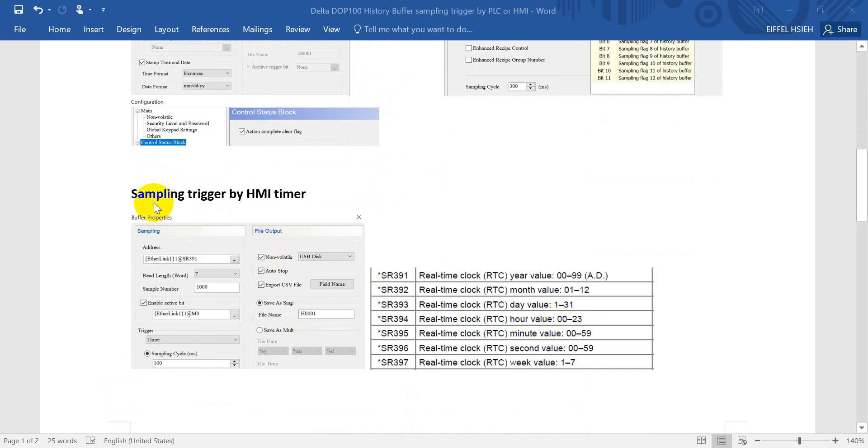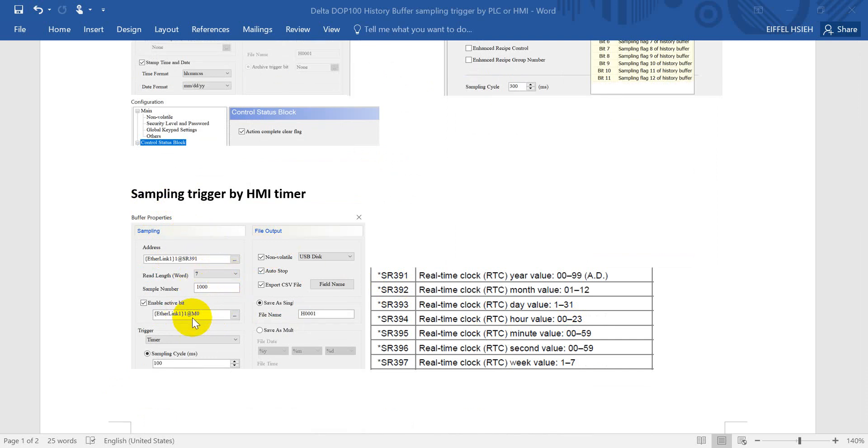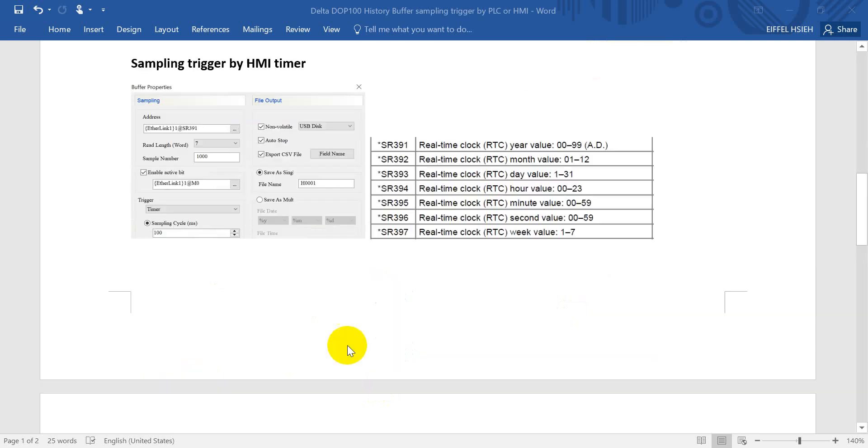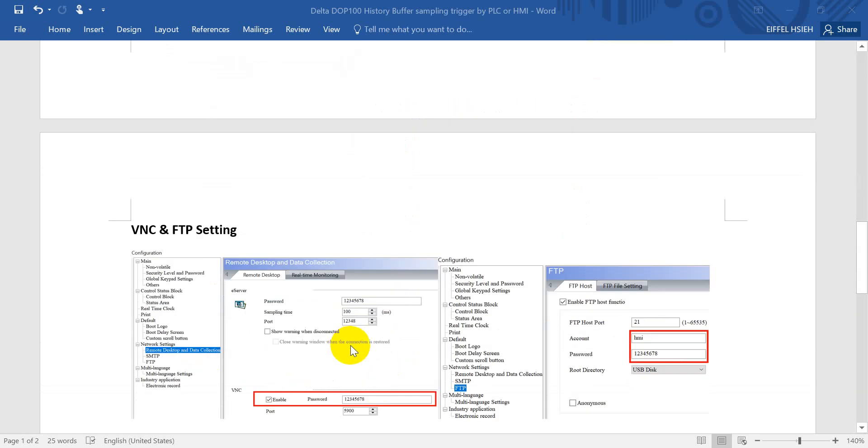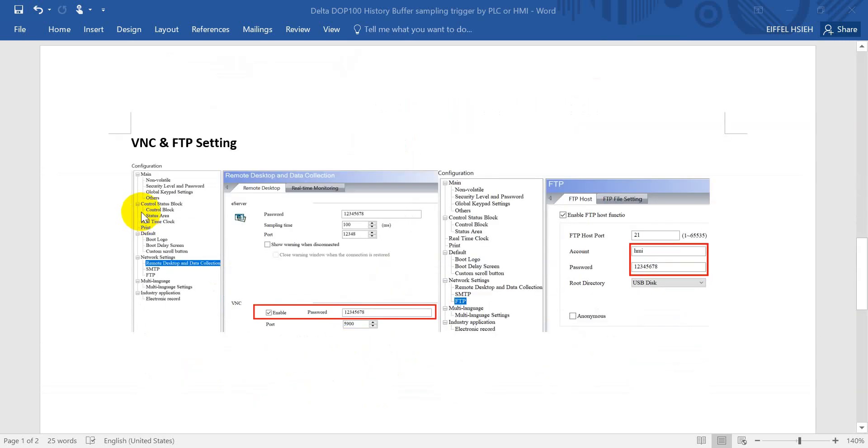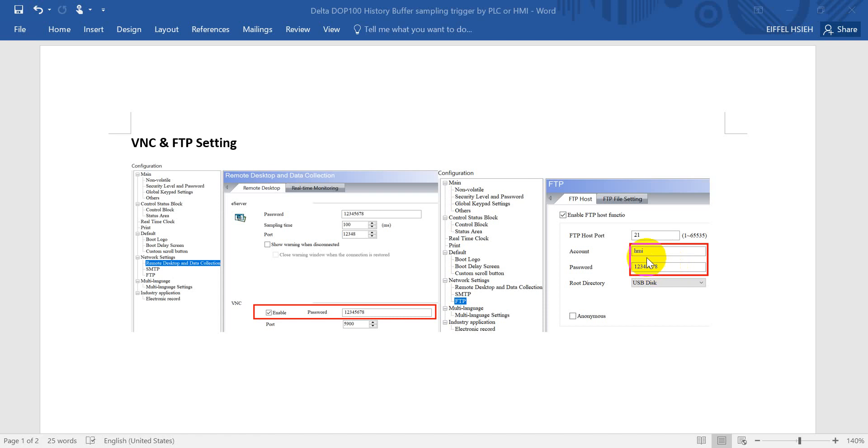Another way is triggered by HMI timer. So again, here is the 391.7 or 1000, then enabled by M0. The default sampling cycle is 100 milliseconds. This demonstration, I will show you via VNC and FTP settings. Remember to enable the VNC and FTP function, and both default passwords are 12345678.